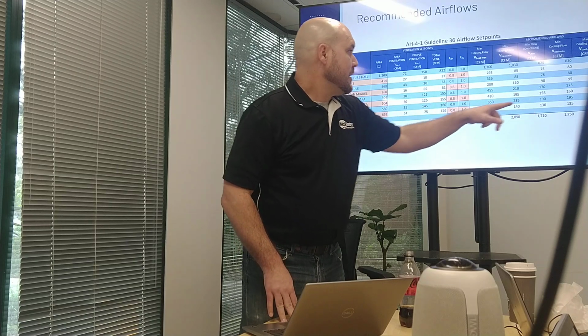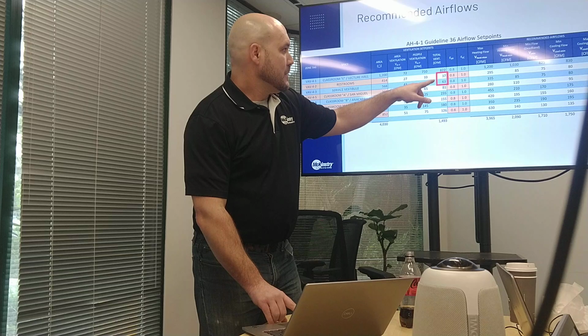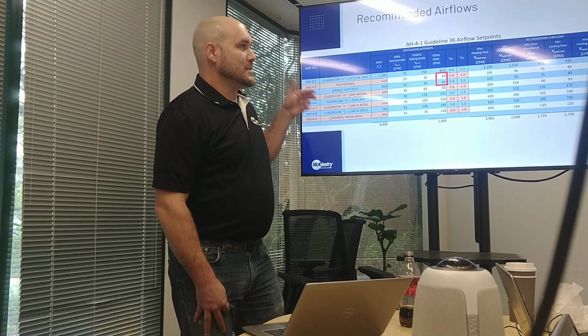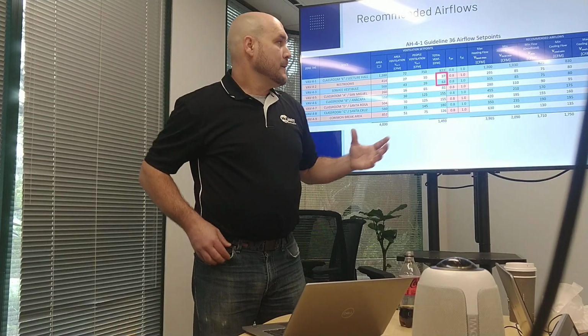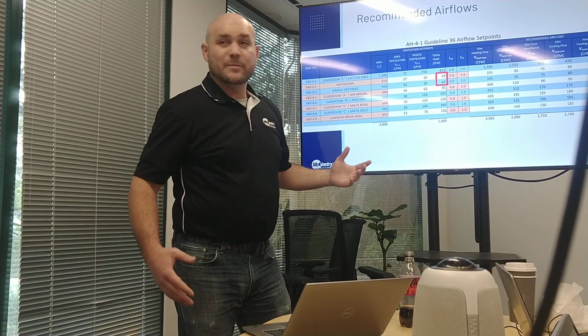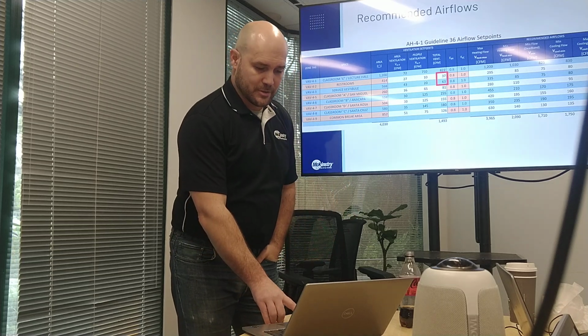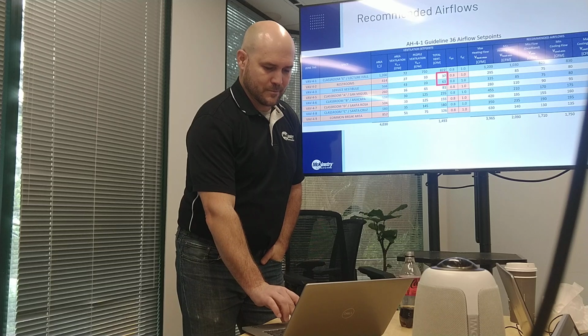We're controlling to 155. These other two zones, though, the 37 and the 63. Well, we're only going down to 75. So what that tells you is that the size of the box is what's limiting these minimum values. So if they were doing a renovation, maybe downsizing those boxes is an opportunity. So you could drive this one down to, I don't know, 40. And restrooms, admittedly, aren't a great example because their airflow is more dictated by exhaust requirements, but the point remains.